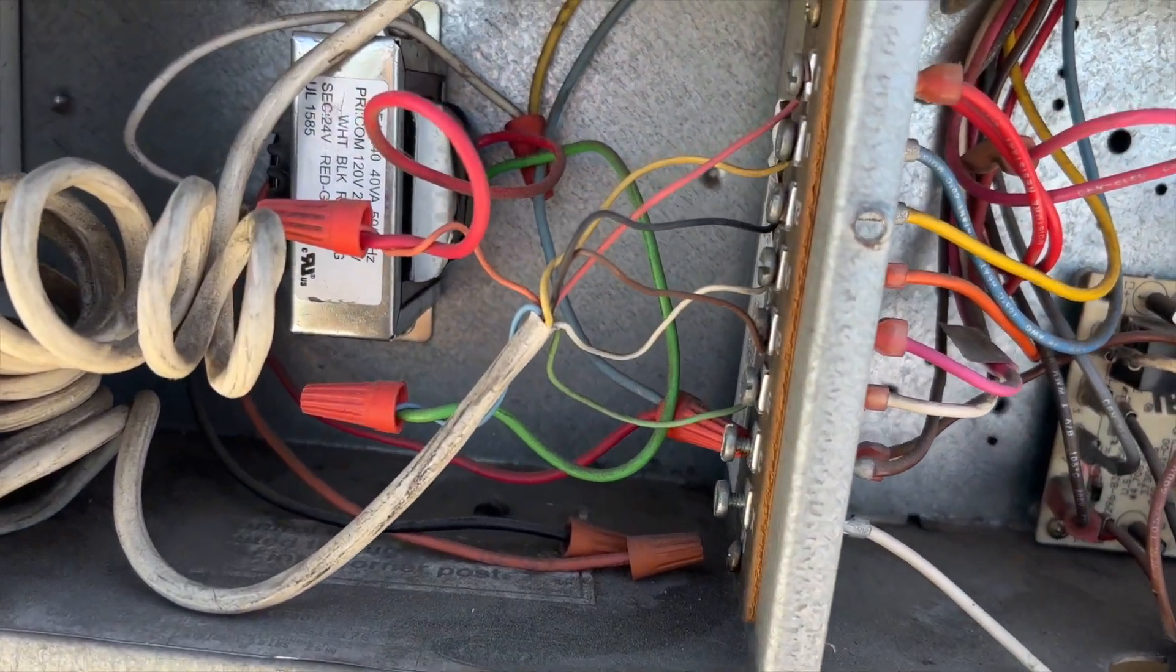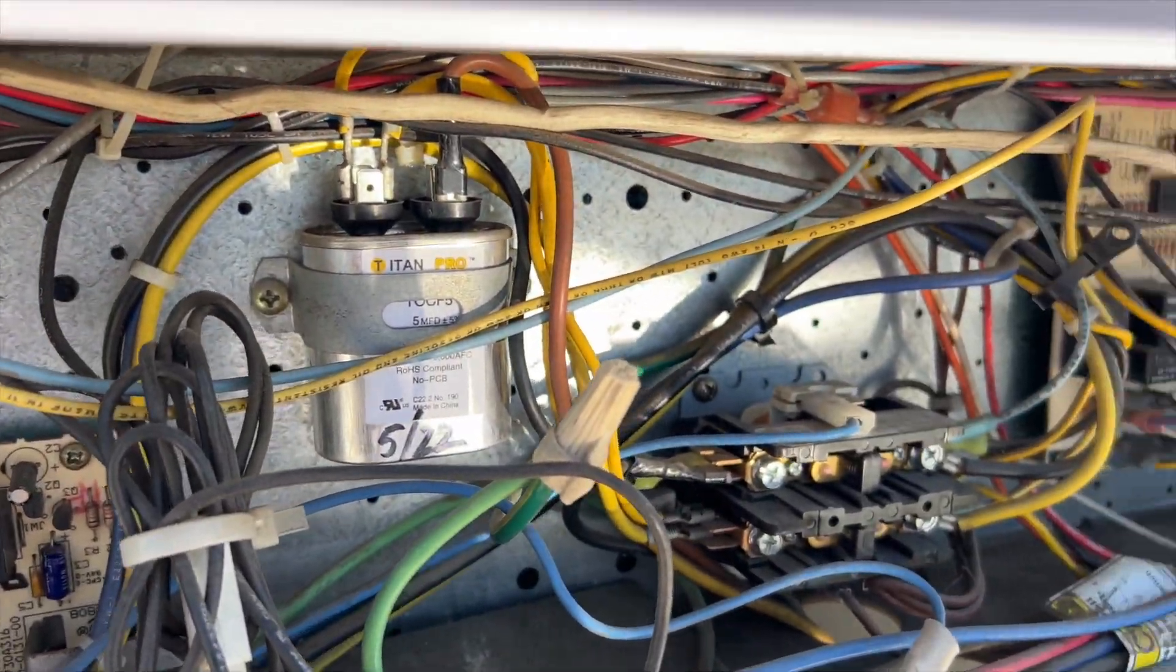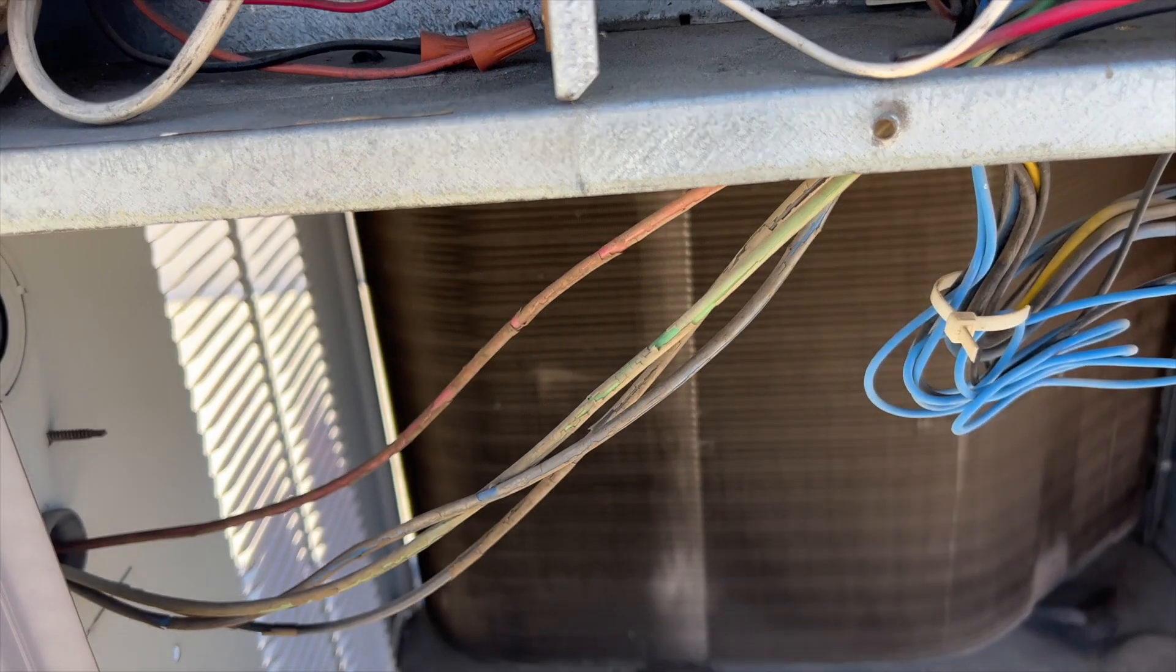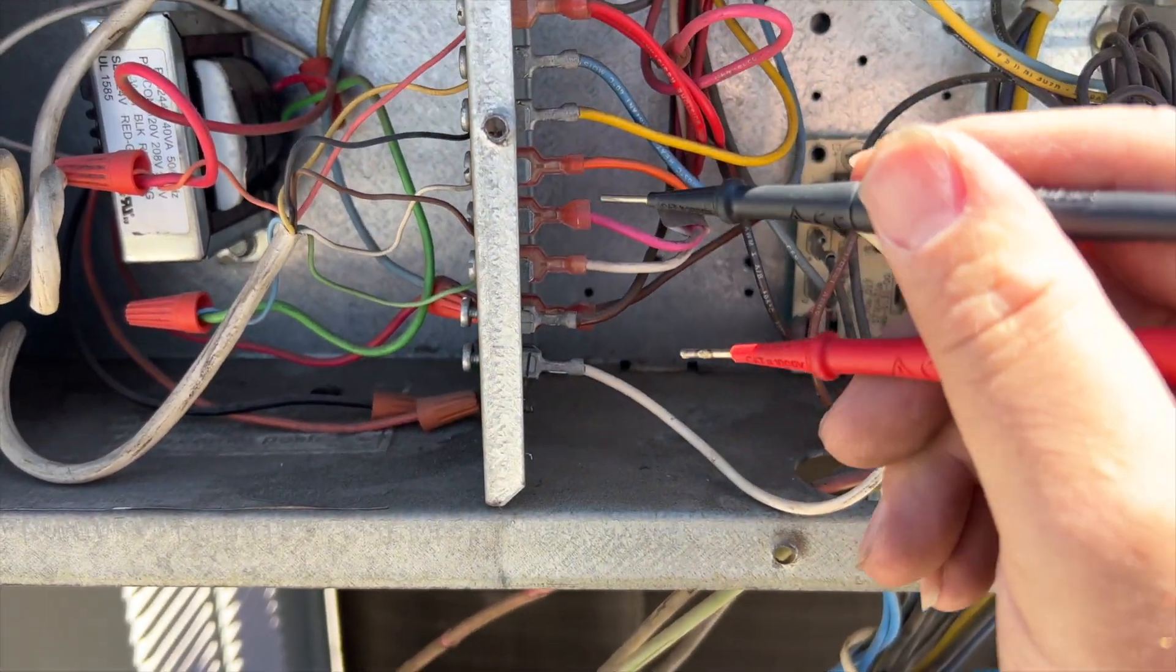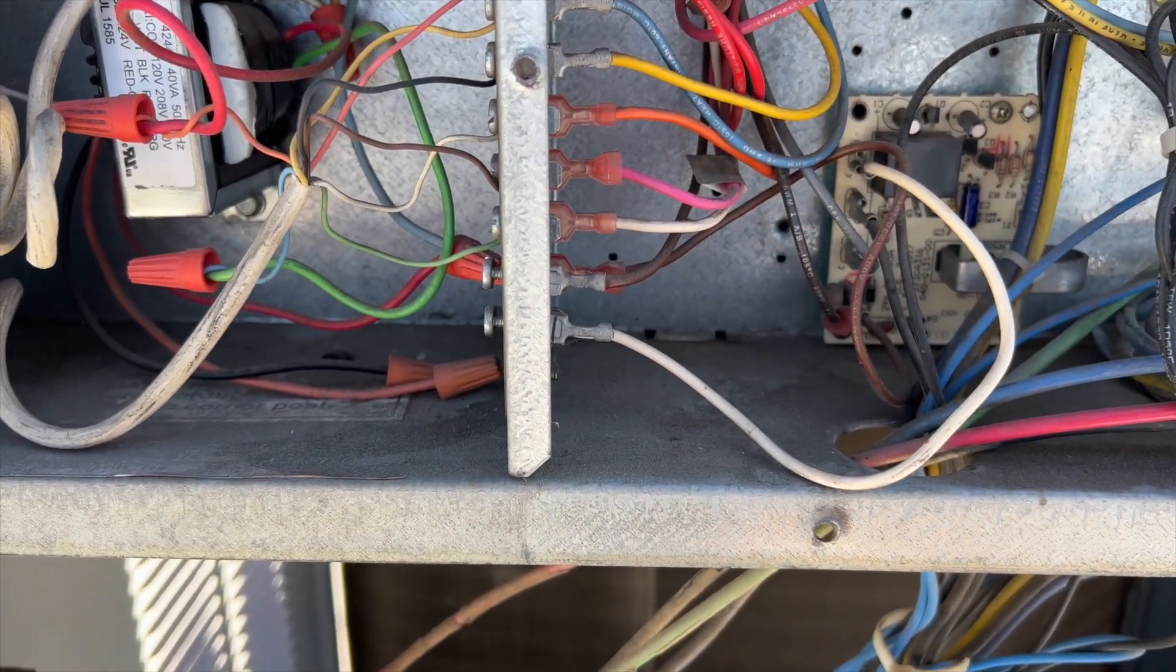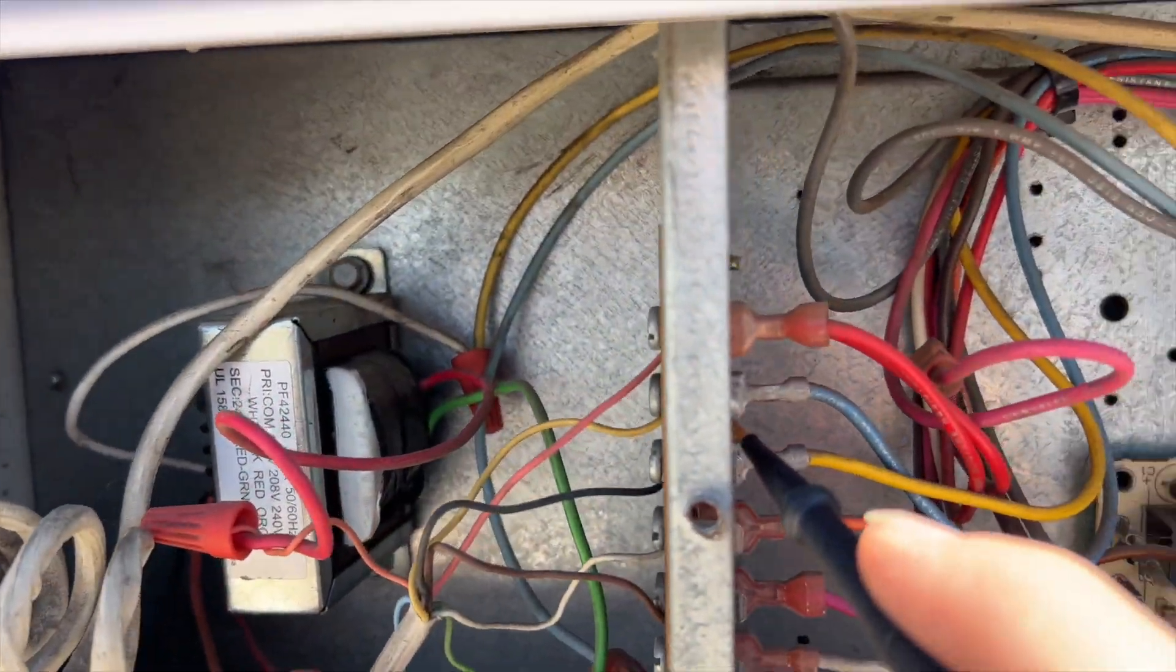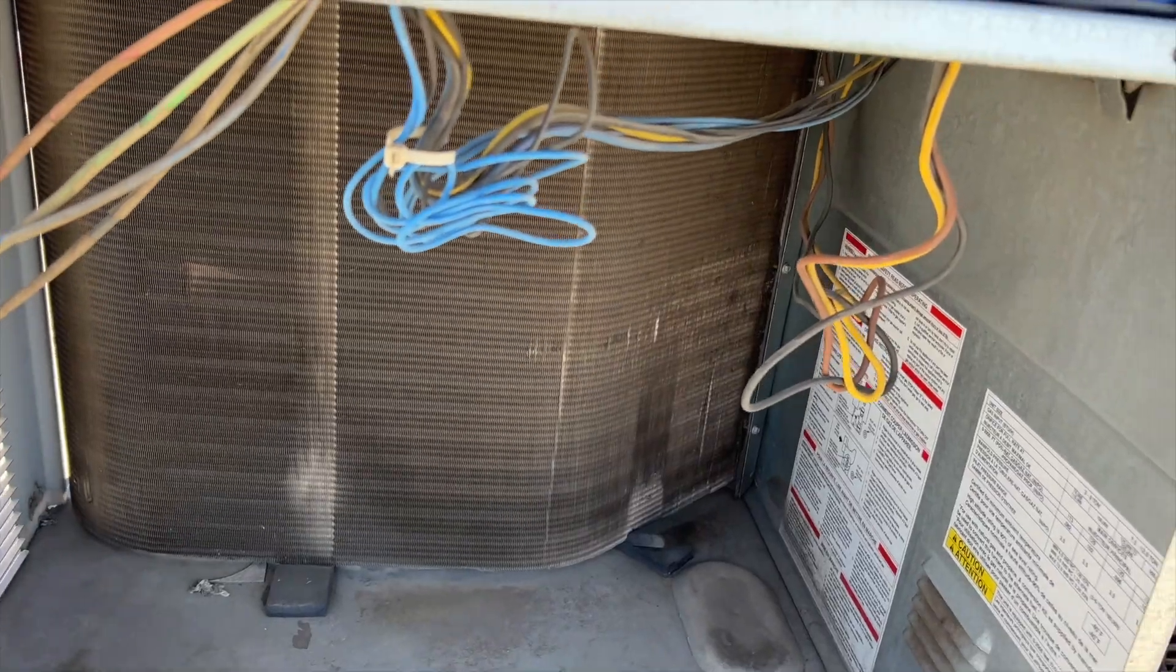We're back on the roof, everything's running, the blower's on now. This is one of those Carriers which requires a call for G as well as Y because they got all these circuit boards but they can't make it turn on automatically. That's just too much to ask, so annoying. But anyway, you can see here if we go from G to C we have 24 volts, and then if we go Y1 to C we have 24. So the thermostat's actually calling for G and Y.